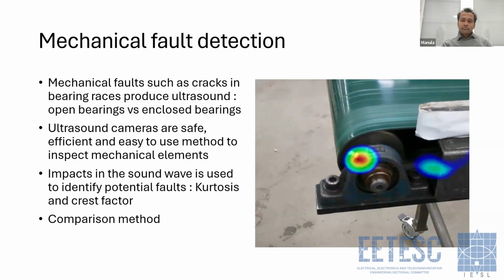So there are different metrics that are used to define these fault levels in acoustic cameras. For example, kurtosis and crest factor are statistical metrics that are often used to define how impulsive the sound wave is. And of course, users can compare different or identical components to get a good comparison. So if one bearing is detected with higher SPL or higher kurtosis and crest factor compared to the identical one, we know something is wrong with the first bearing. That kind of comparison method can also be used for mechanical fault detection.